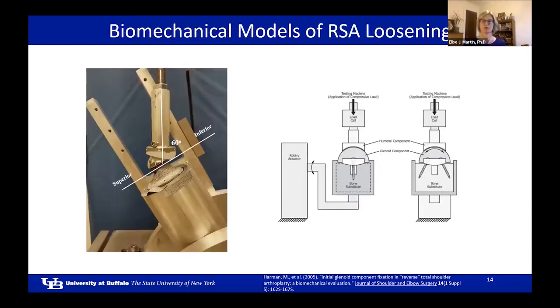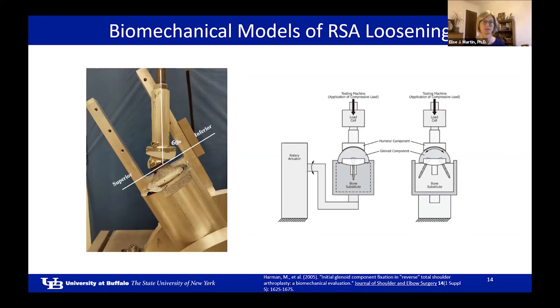This testing protocol uses a simulated abduction protocol to test RSA glenoid baseplate loosening, mimicking shear and compressive forces at the angle of maximal joint reaction forces. A major advantage is that its simplicity allows continuous displacement measurement throughout the entire test. However, to more thoroughly measure displacements, we are developing a system that rotates the sample through an abduction arc to more accurately represent forces experienced by the implant while still continuously measuring displacements, more closely following ASTM guidelines.